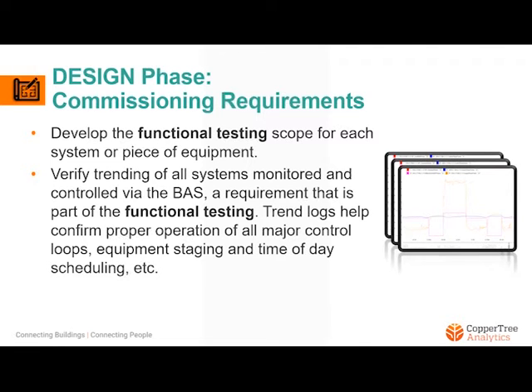Central to the commissioning requirements for the design phase is the development of the functional testing scope for each system or piece of equipment. And since trend logs are essential to the verification of system functionality, there needs to be a validation process to make sure all inputs, outputs, set points, and other variables are being trended accurately. This will help to confirm proper operation of all major control loops, equipment staging, and time of day scheduling.